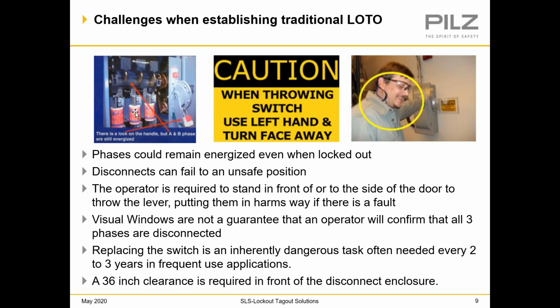Here are some of the challenges of traditional LOTO, or lockout, using a disconnect and locking it out. First of all, in the upper left corner, you see a picture of a disconnect panel with the disconnect locked to the off position, and we've got a clear plexiglass front to that. But if you notice, two of the three phases are actually still engaged. So even when this is locked out, there is a possibility that you're not really locked out. You actually have two of the three phases in this photograph showing power still being applied and available, and obviously being dangerous to somebody in the zone that this is being sent to.